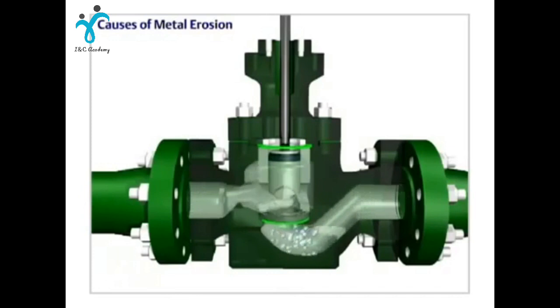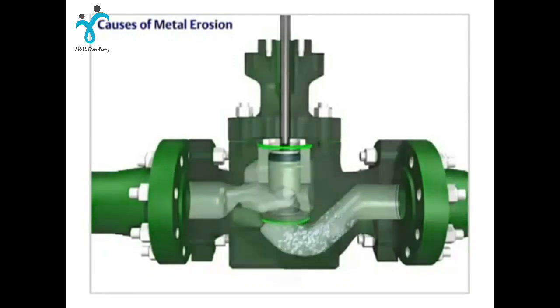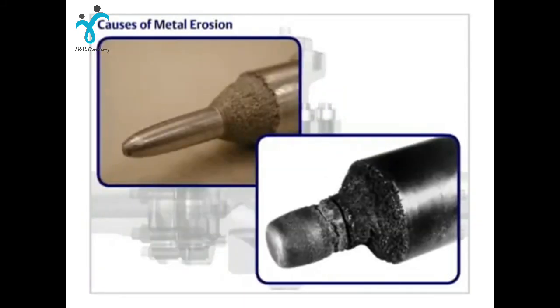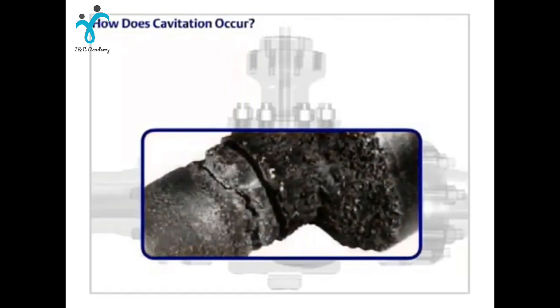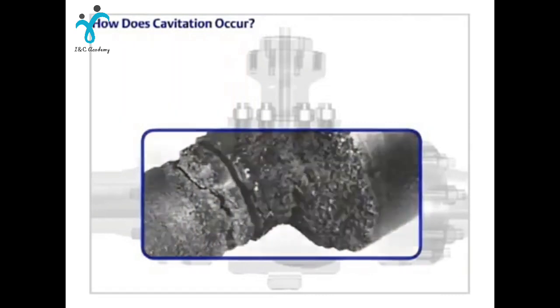Cavitation occurs when the fluid vaporizes then returns to a liquid state as the pressure increases downline. The metal damage caused by cavitation is rough and irregular due to pitting of the surface. Cavitation is a major source of damage in control valves and other components.